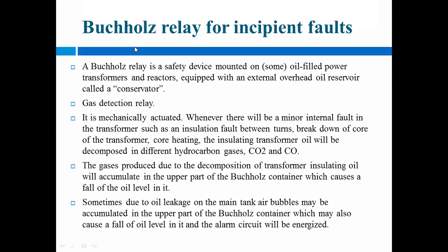In between that transformer tank and that conservator, your Buchholz relay is located. This relay is a safety device mounted on oil-filled power transformers and reactors equipped with an external overhead oil reservoir, that is the conservator.